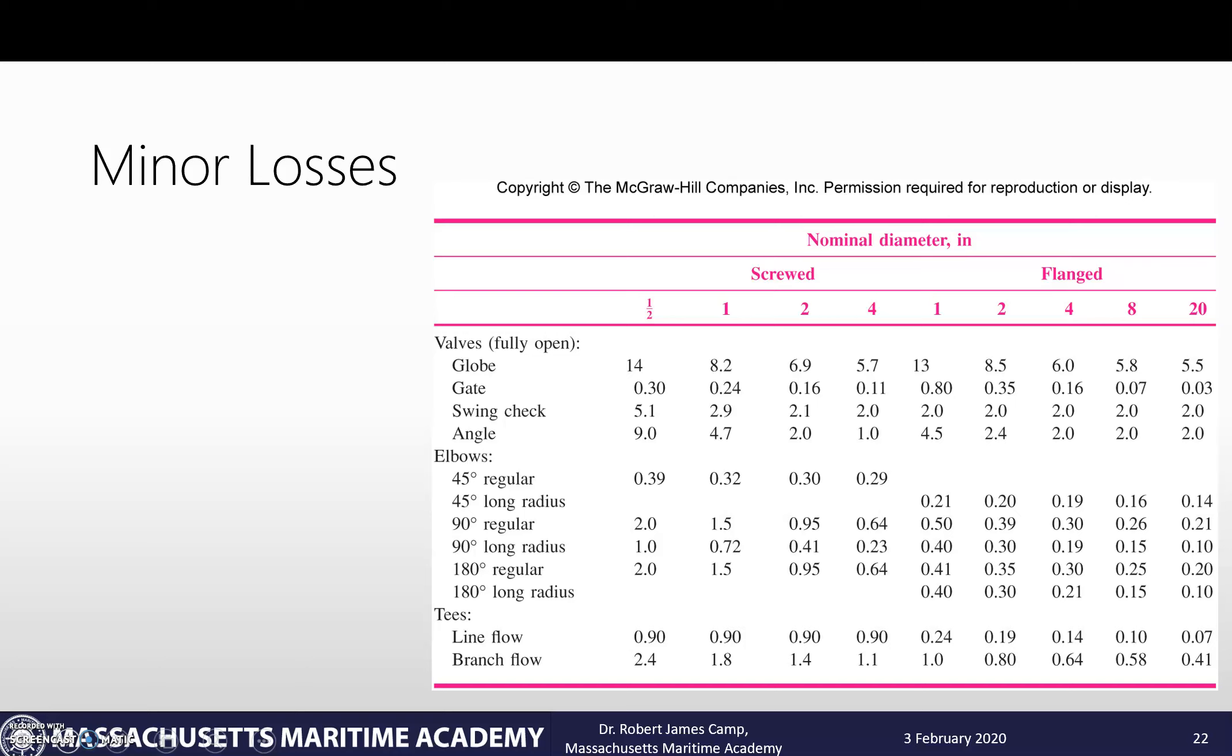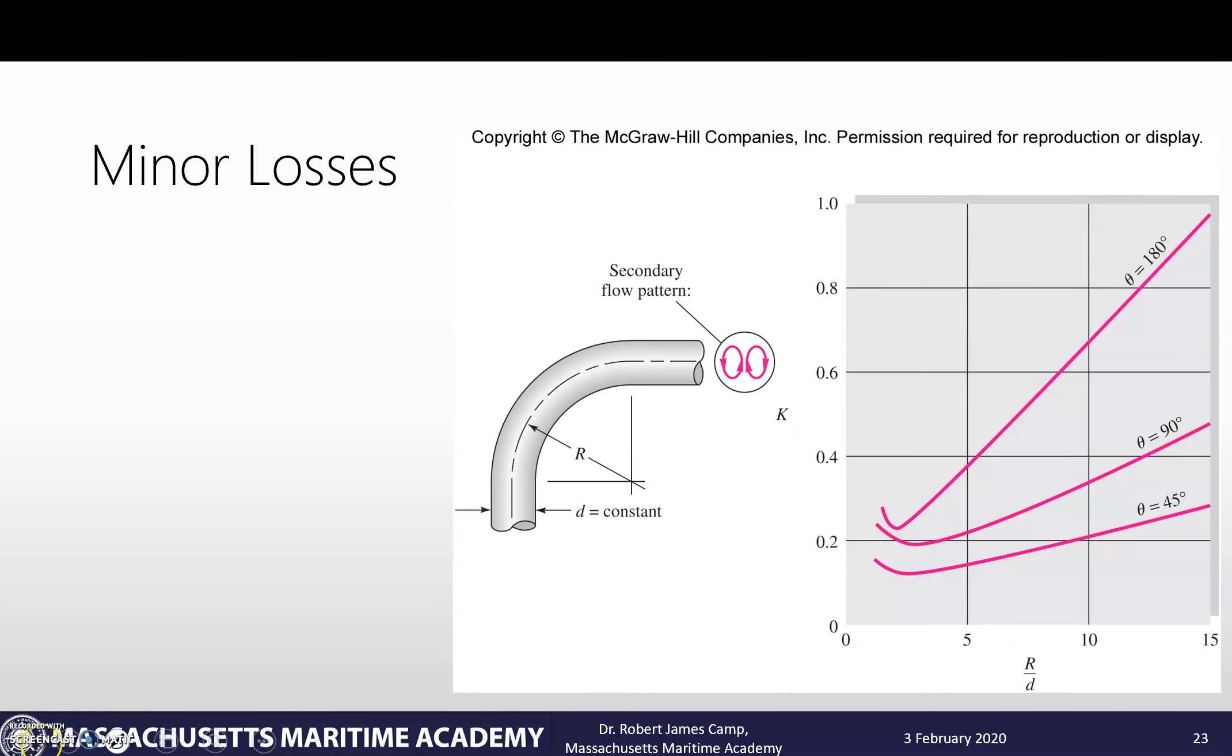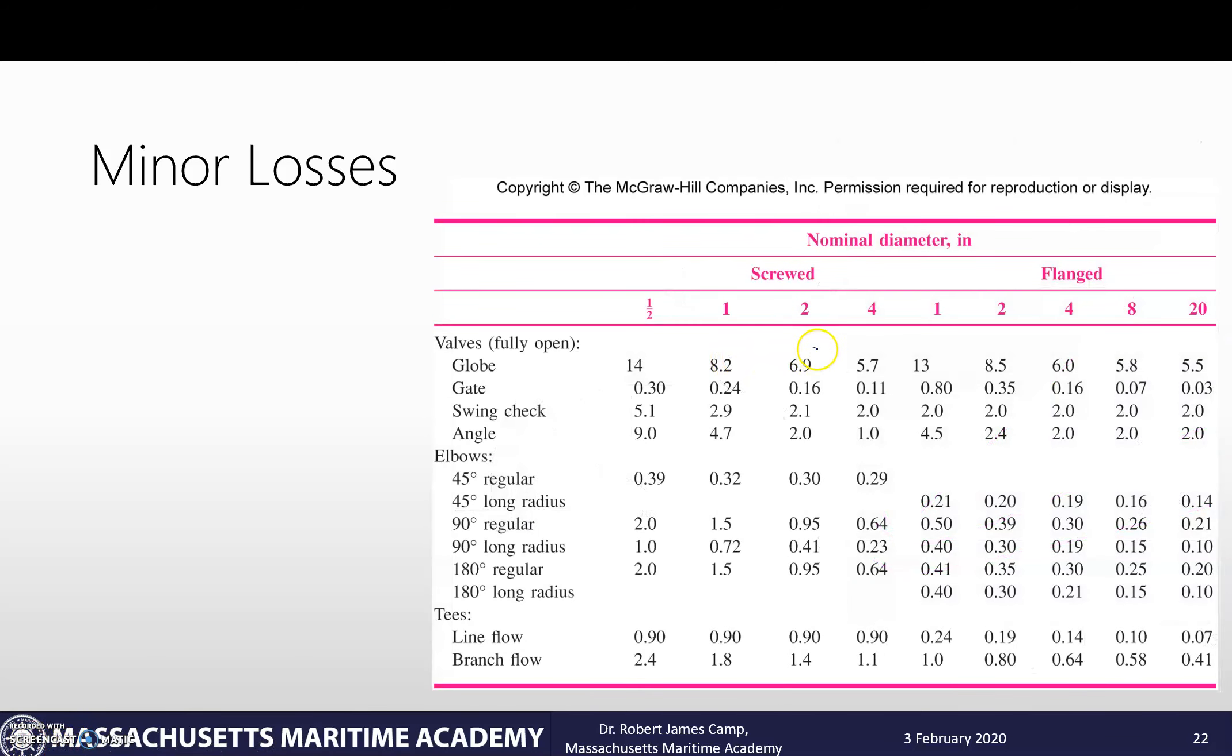Now we have our open globe valve. We'll assume it's screwed - why am I assuming it's screwed? Because I have screwed pipe later on. So we look: two inches screwed, fully open globe valve, right there we have a value of 6.9.